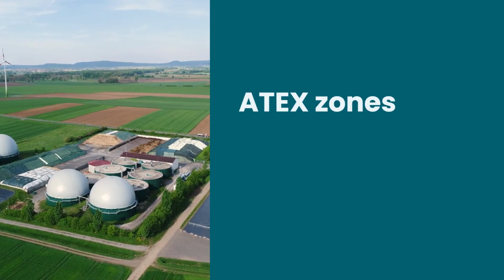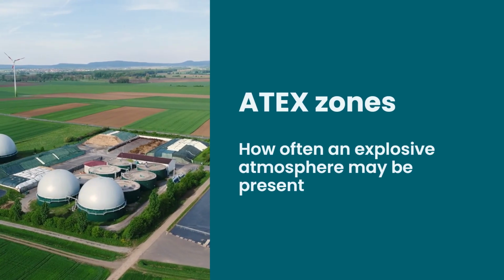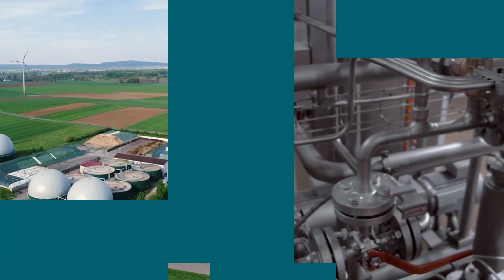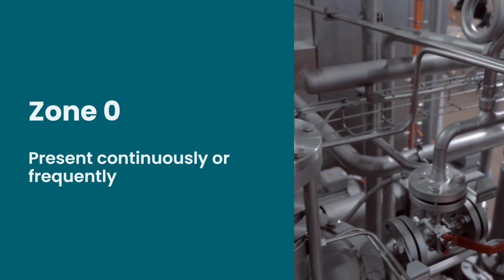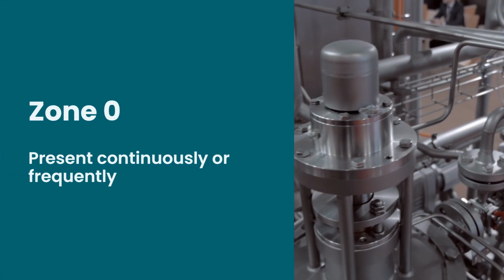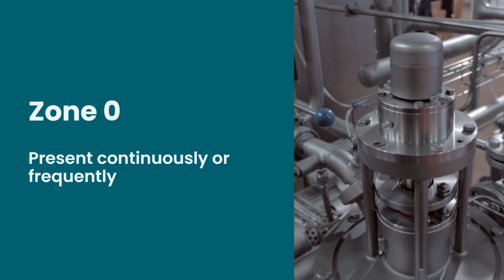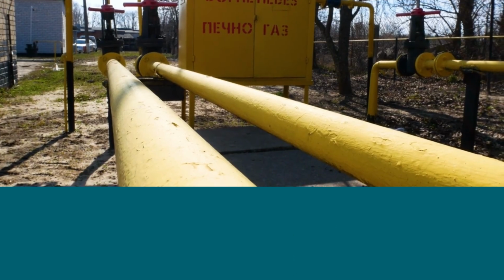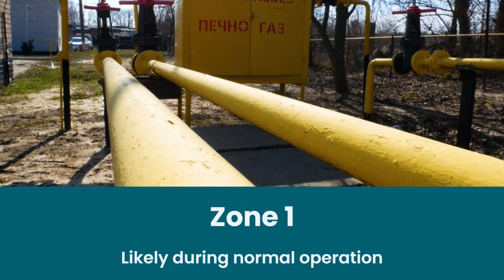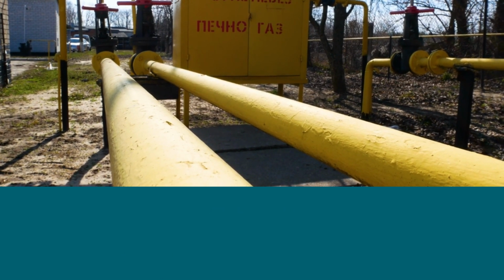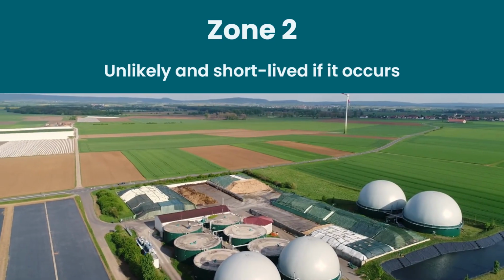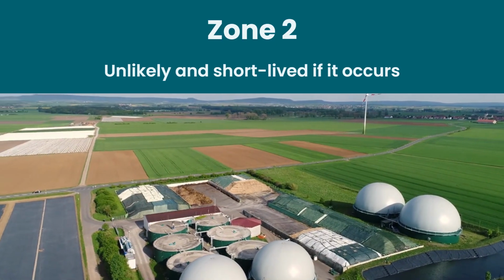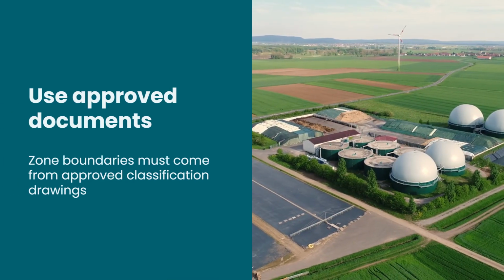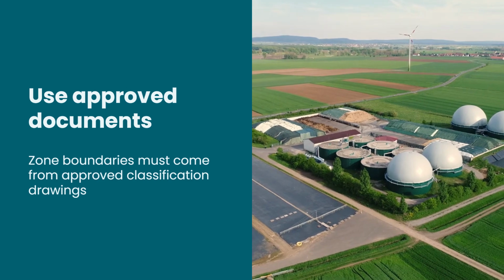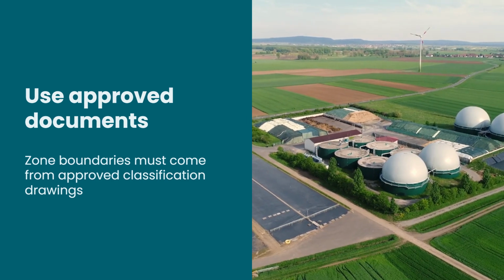ATEX zoning describes how often an explosive gas atmosphere may be present. Zone 0 is where an explosive atmosphere is present continuously, for long periods, or frequently. Zone 1 is where an explosive atmosphere is likely during normal operation. Zone 2 is where an explosive atmosphere is unlikely and short-lived if it occurs. Zone boundaries must come from approved classification drawings, P&IDs, procedures, and risk assessments.